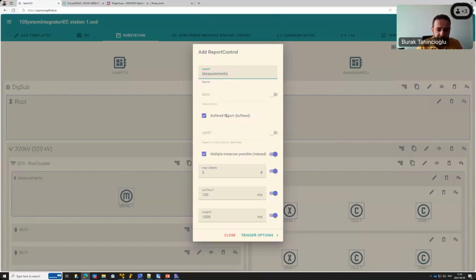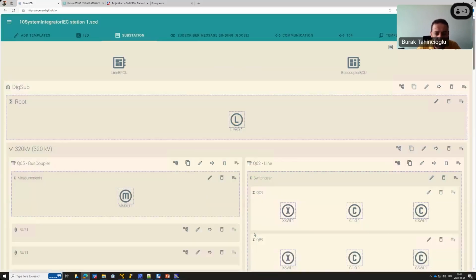And OpenSCD asks me if it's buffered or unbuffered. For measurements, maybe it's not necessary to buffer them and really tire the buffer, because they will change based on the deadband values every now and then. I want to use the buffer for important events, not for measurements. And I want to have 5 clients. What is this 5 clients information? This is the number of clients in the substation that you want to have. You also get this information from the specification. You know you have one HMI, you have one gateway, and then you also leave one spare control block instance for a test client like IEDScout, for instance, or for yourself. So 5 is a good number, maybe. Then you go for triggering options.